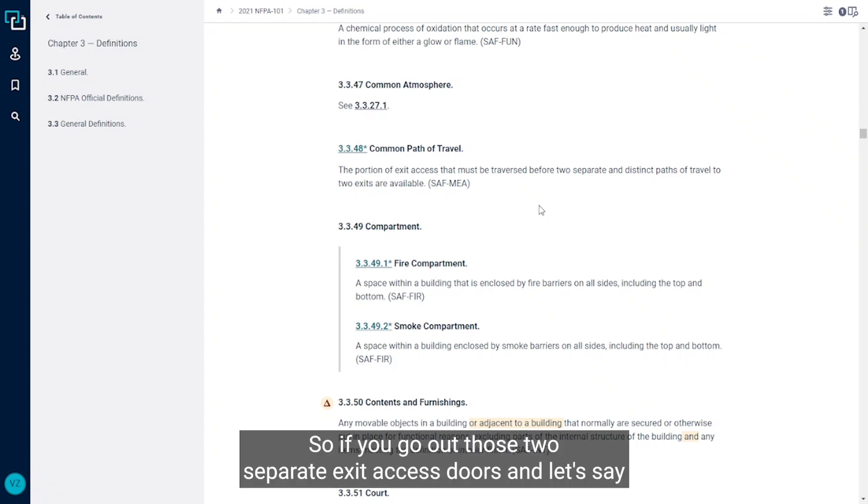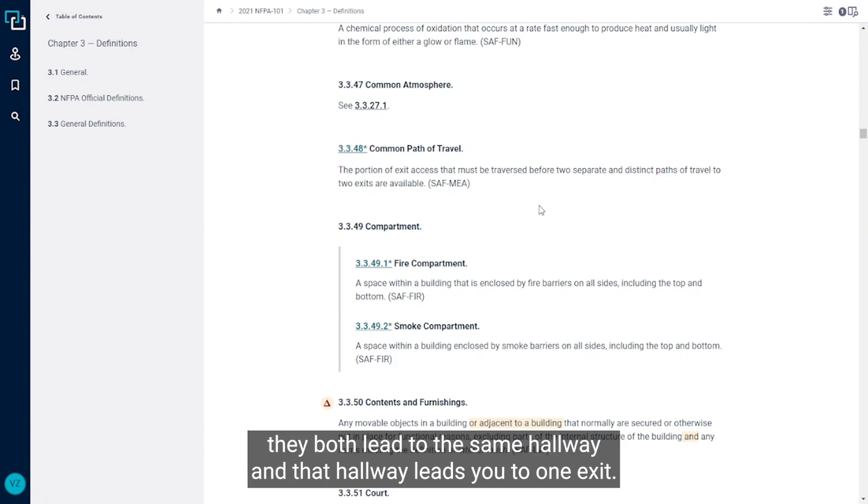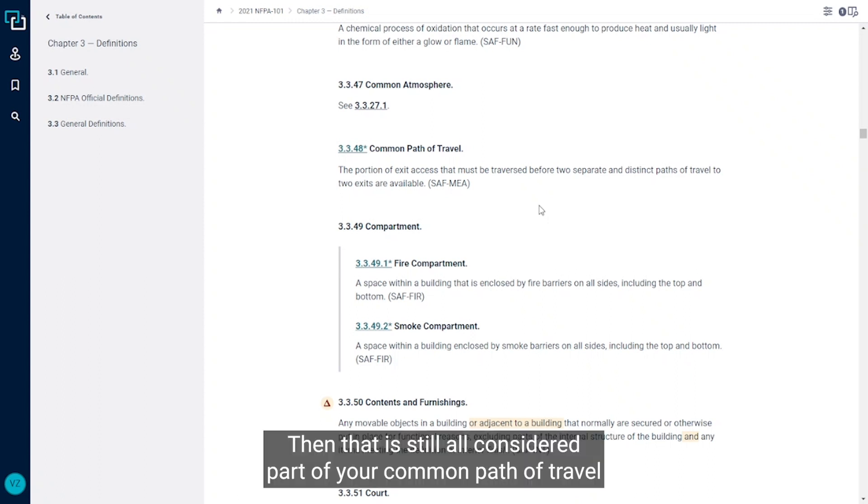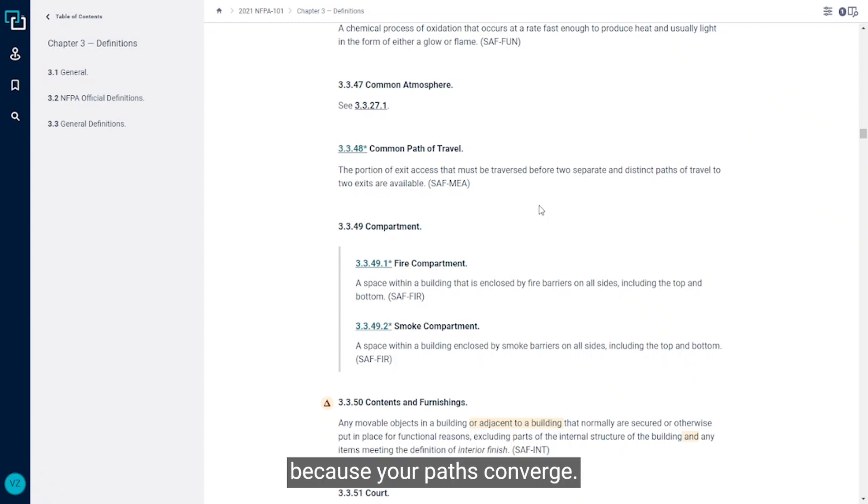So if you go out those two separate exit access doors and let's say they both lead to the same hallway and that hallway leads you to one exit, so you go out those doors and in both cases you have to turn right, then that is still all considered part of your common path of travel.